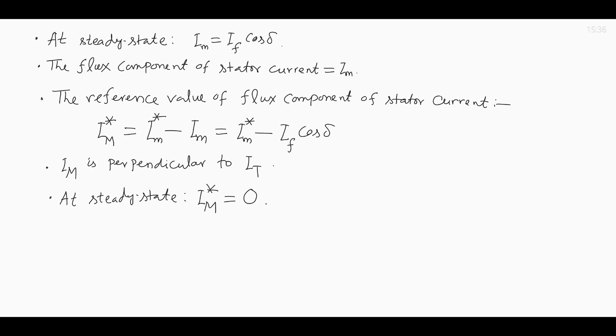I am going to explain this. The current components IT star, the torque component or active component reference value, and the injected magnetizing current component Im star, the transient period magnetizing current reference value, are controlled in this vector control scheme by the synchronous frame current control technique, just as we have discussed in the induction motor drive, synchronous frame current control.